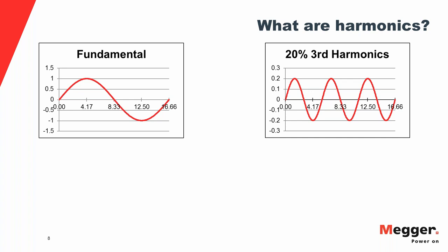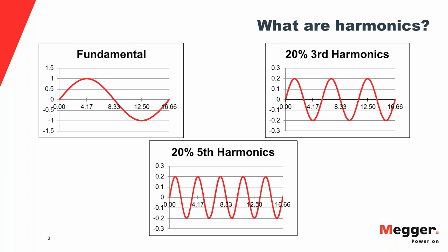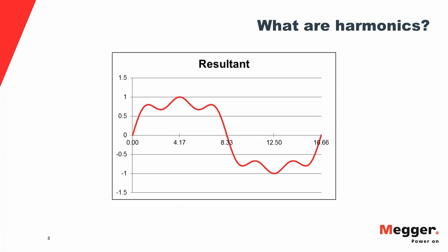Taking another wave with the same 16.66 ms time axis, we see three cycles — meaning its frequency is three times higher — with a magnitude of 0.2, which is 20% of the fundamental. A third waveform shows five cycles in the same time, again at 20% magnitude. When these three waveforms with different frequencies are mixed together, the result shows how a waveform gets distorted because of the presence of different frequency components.